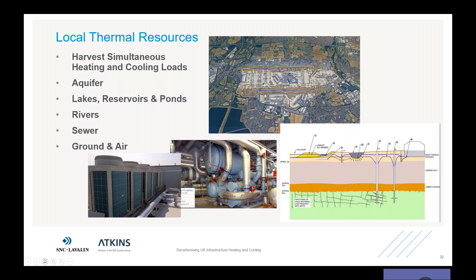There were also investigations into the aquifer below the site, the lakes, reservoirs and ponds around it, rivers, the sewer system, and ground and air sources. All of these systems would be coupled with heat pumps to interface with them, and the simultaneous heating and cooling loads would also be dominated by the application of heat pumps, integrated with thermal storage for balancing.